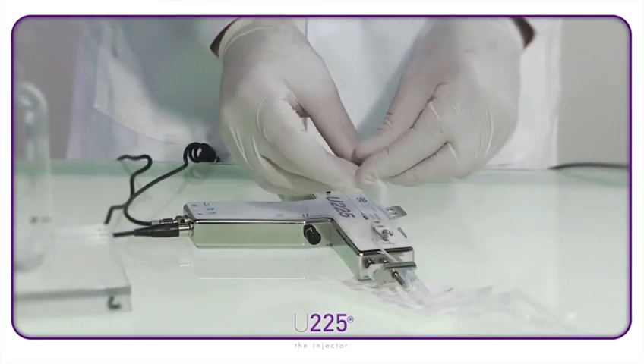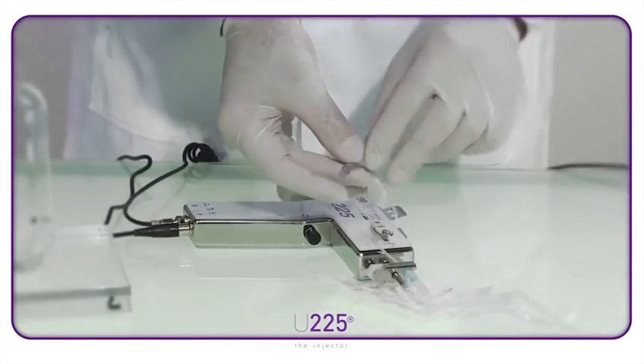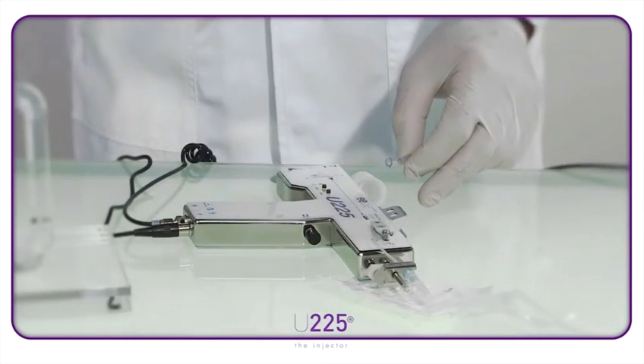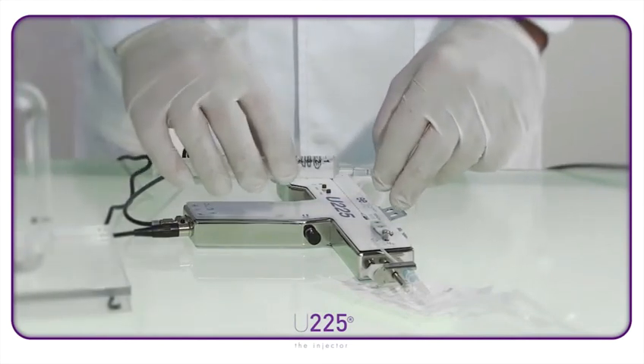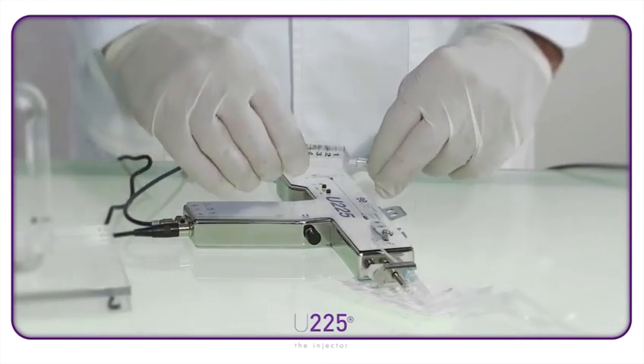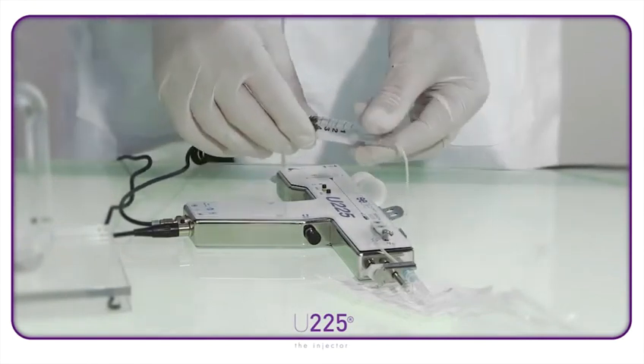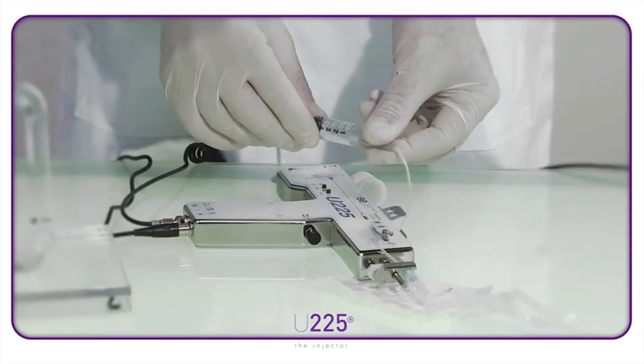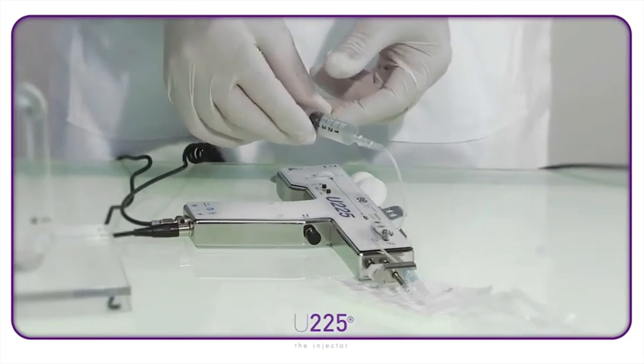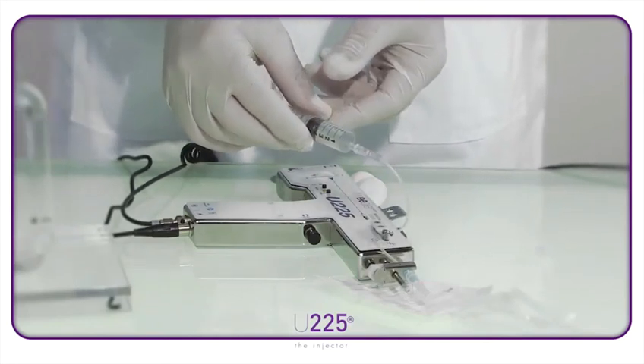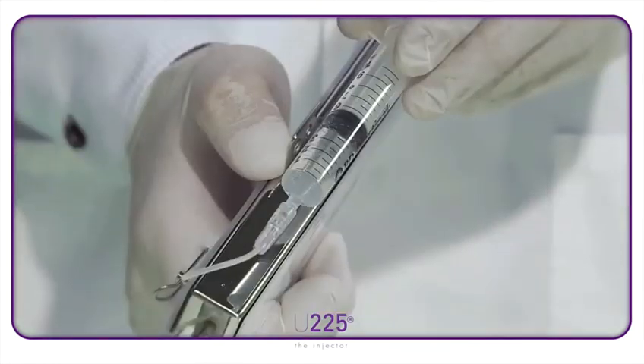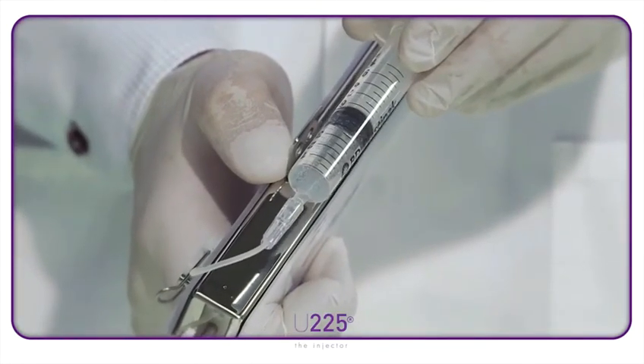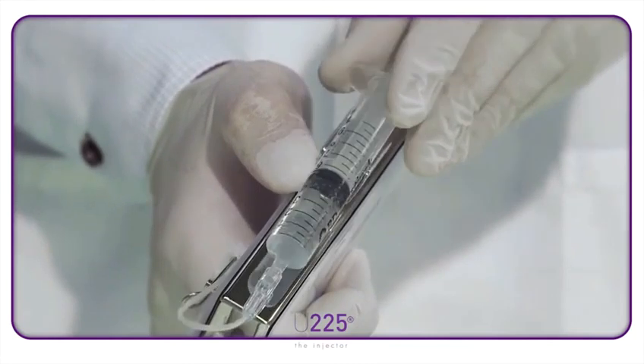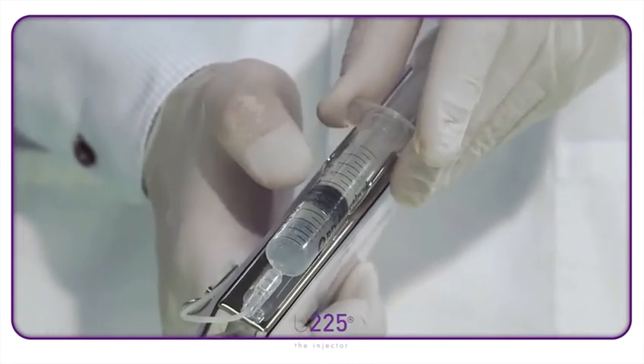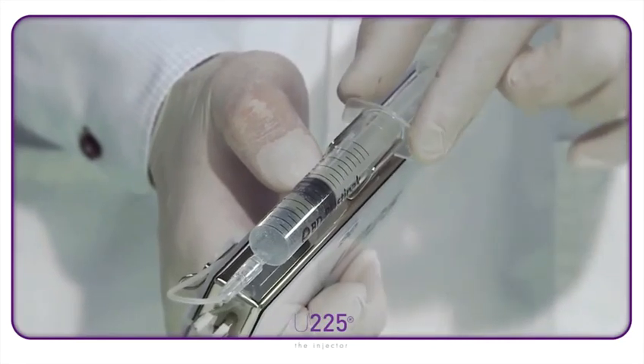Put the injector down and undo the plug at the very end of the tube to insert a previously prepared syringe. Make sure that the tube is tightly connected to avoid it falling out with the pressure of the syringe pump. Place the syringe on the metal holder with the measuring marks uppermost.